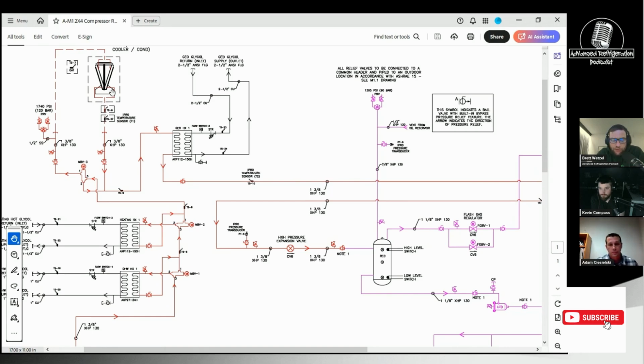So it's still running those temperatures, even though you said 1,200 pounds, when you boost it up in the heat reclaim, and you're still getting that drop leg temperature down to 60. You're still a supercritical fluid, right? So you're still basically not a liquid. We can't technically call it a liquid at that point, even though it's really cold. Correct? That's correct.